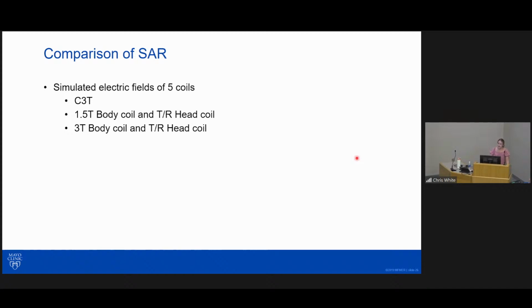In order to compare SAR, the simulated electric field of the compact 3T scanner was compared to a 1.5T and 3T whole body scanner with both a TR head coil and a body coil, using a human body model. From this data, SAR spatial maps were calculated using the following formula, where E is the electric field, and sigma and rho are the conductivity and density of the tissue respectively. Spatial maps of the tissue conductivity and density were obtained from those same human body models.